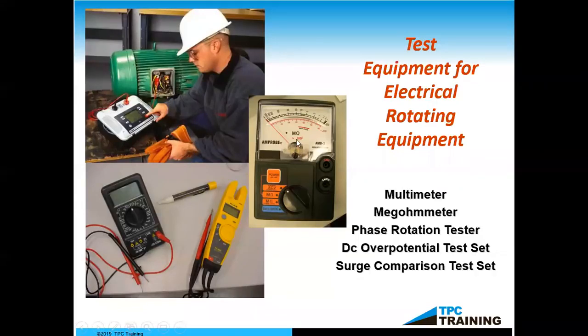Then the one in the middle, from Amprobe, has an M and then an ohm symbol behind it. That's a mega. And that mega is going to be used to test the insulation. The regular multimeter we're going to use to test the windings, and if we were troubleshooting and had to trace voltage with the multimeter, we definitely could do that.